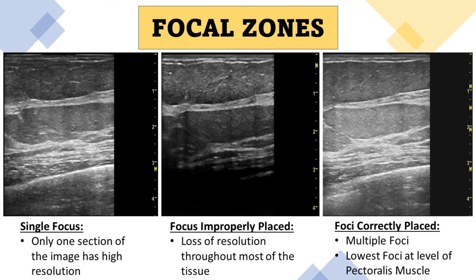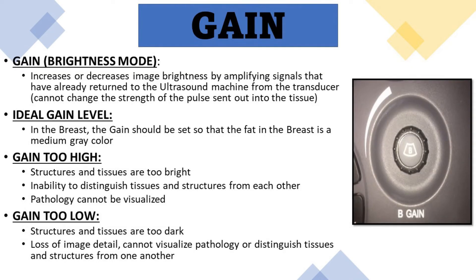There are three primary brightness controls on an ultrasound machine: gain, TGC, and output power. The gain control increases or decreases image brightness by amplifying signals that have already returned to the ultrasound machine from the transducer — you cannot change the strength of the pulse sent into the tissue with the gain control. In the breast, the gain control should be set so that the fat in the breast is a medium gray color.